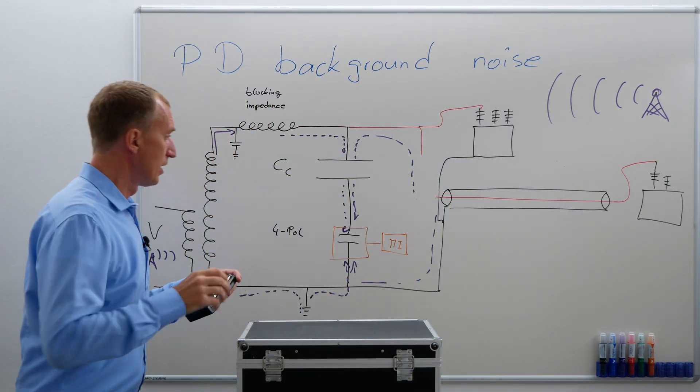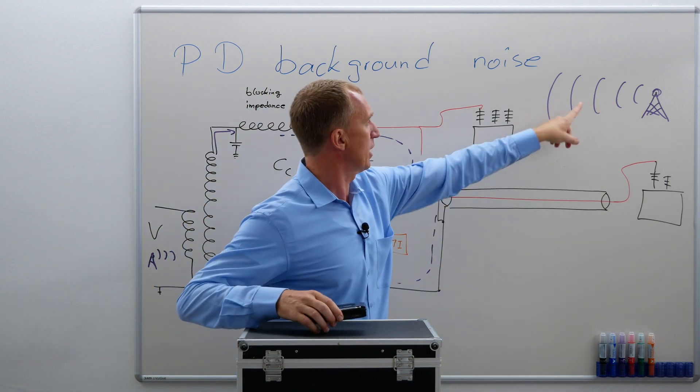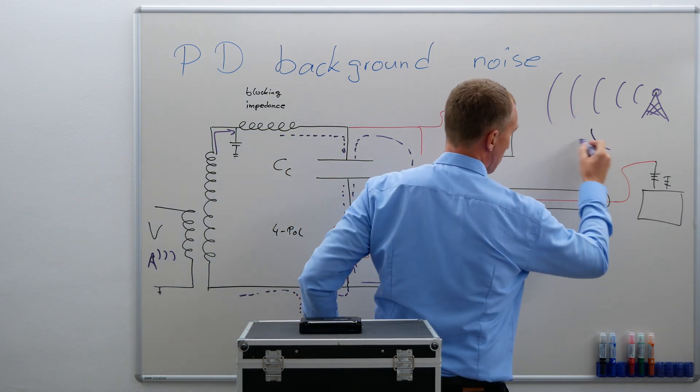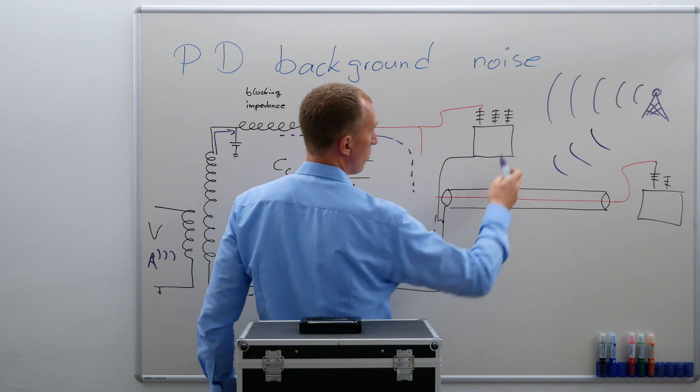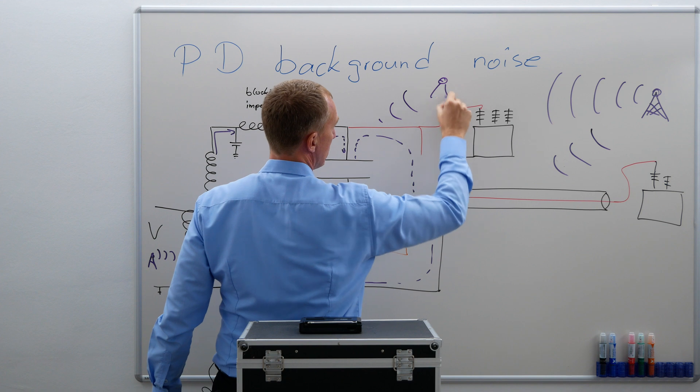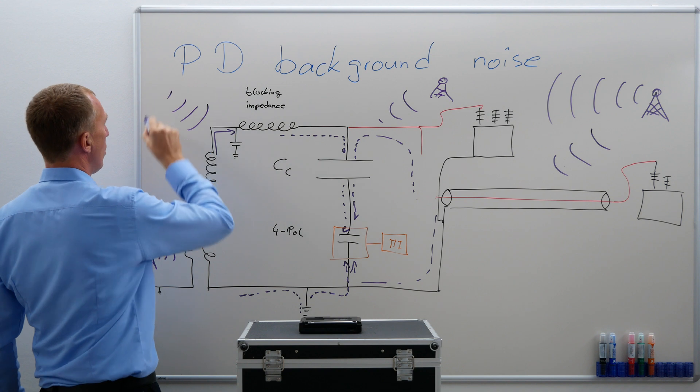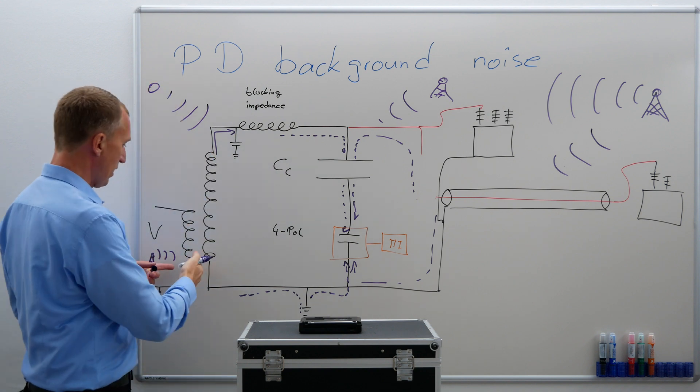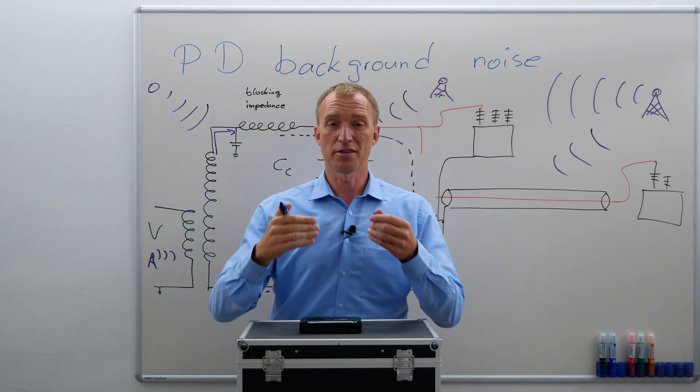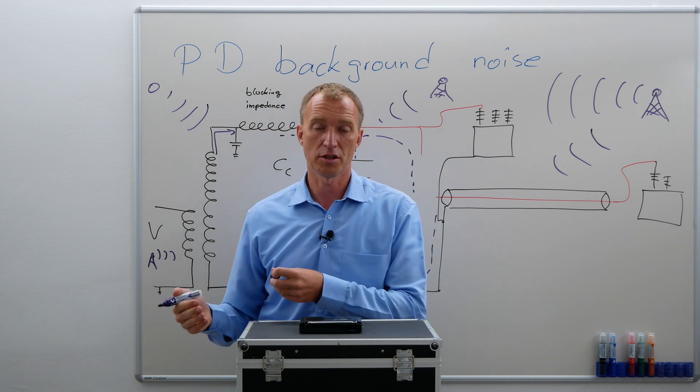We talked about that we can have different kinds of airborne noise that can, of course, couple into our test object. We talked about this before, it can couple in the test object, but it can also couple in our high voltage connection. It can couple into our blocking impedance. It can couple into our voltage source. So as a matter of fact, noise is everywhere and this is one of the biggest challenges. We have to fight noise in order to make a proper partial discharge measurement.